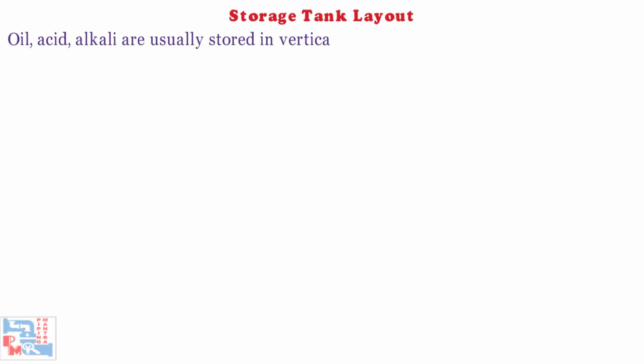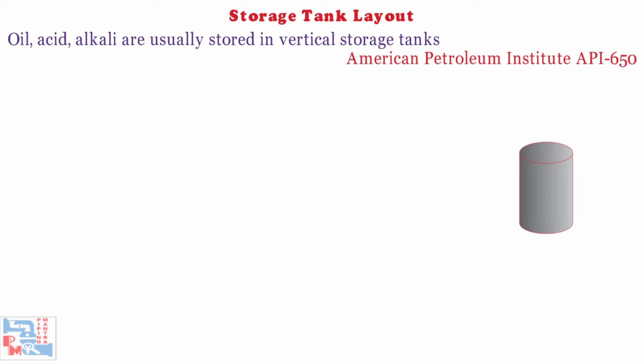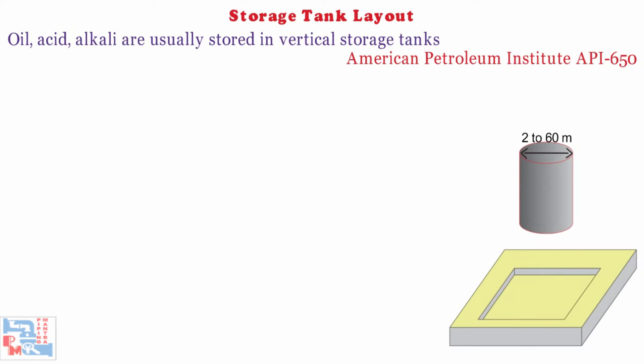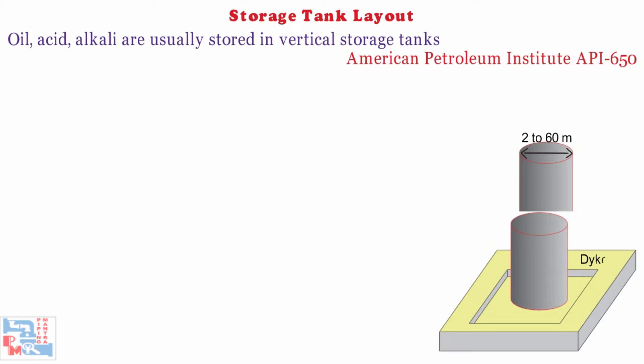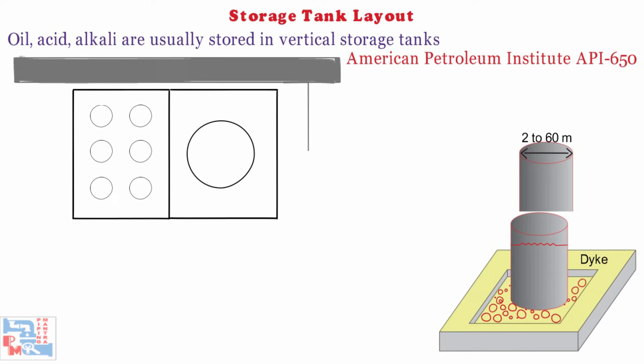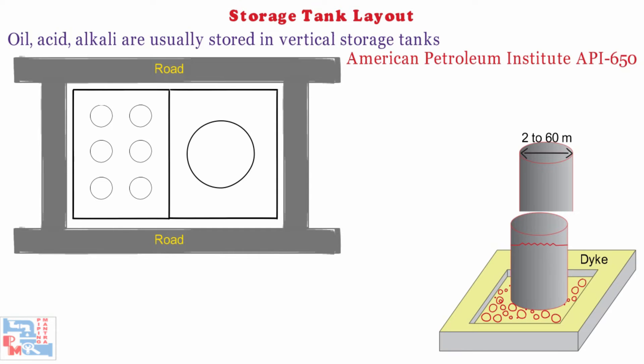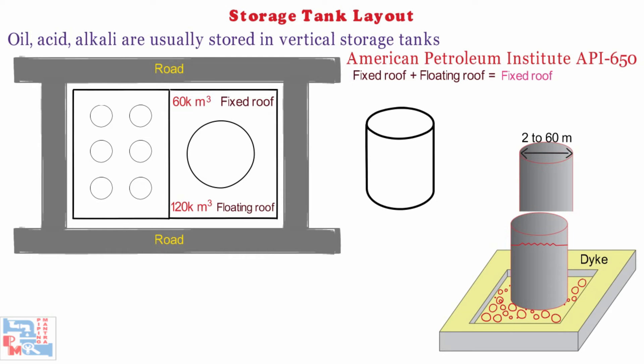Oil, acid, and alkali are usually stored in vertical storage tanks designed as per American Petroleum Institute API 650. These tanks can have different sizes ranging from 2 to 60 meters in diameter or more. They are generally installed inside containment basins called dikes to contain spills in case of tank rupture. Petroleum storage tanks shall be in diked enclosures with roads all around. The aggregate capacity of tanks in one diked enclosure shall not exceed 60,000 cubic meters for fixed roof tanks or 120,000 cubic meters for floating roof tanks. A group containing both types shall be treated as fixed roof tanks for these limits.